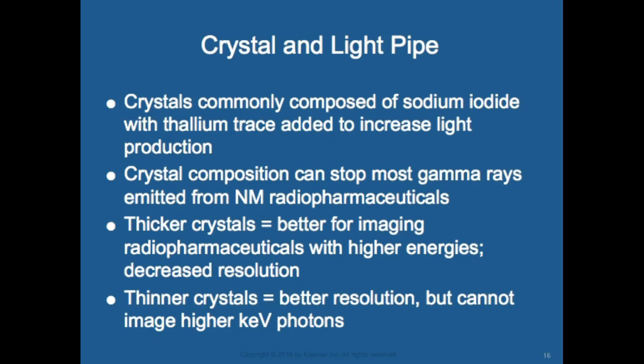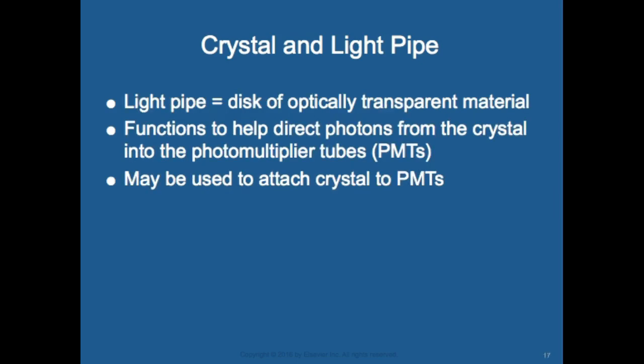Crystals are commonly composed of sodium iodide with thallium trace added to increase light production. Crystal compositions can stop most gamma rays emitted from nuclear medicine pharmaceuticals. Thicker crystals are better for imaging radiopharmaceuticals with higher energy but you lose resolution; thinner crystals have better resolution but can't handle higher keVs. A light pipe is a disk of optically transparent material whose function is to help direct photons from the crystal into the photomultiplier tubes.